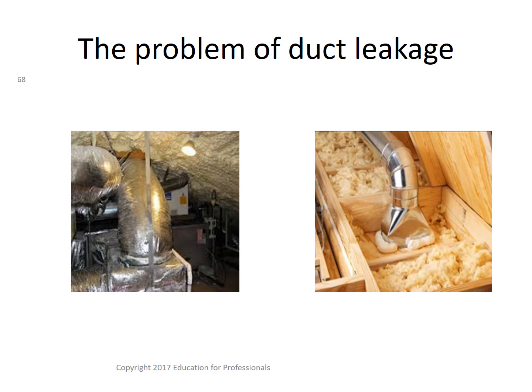So any leaks in the return side of the air handling unit can draw these fumes into the air conditioning system, and this creates indoor air quality problems that could be serious. So the heating and cooling contractor should use proper materials when sealing duct work, in particular duct sealing mastic. And duct insulation does not provide an airtight seal. We're just keeping that in mind.